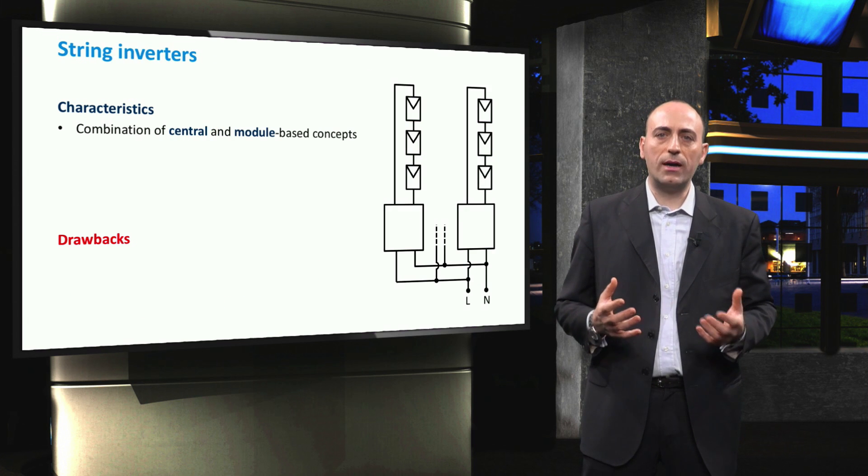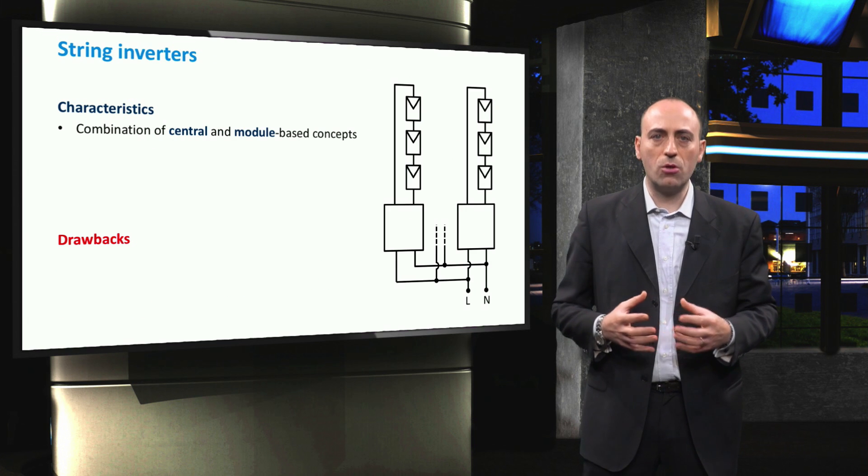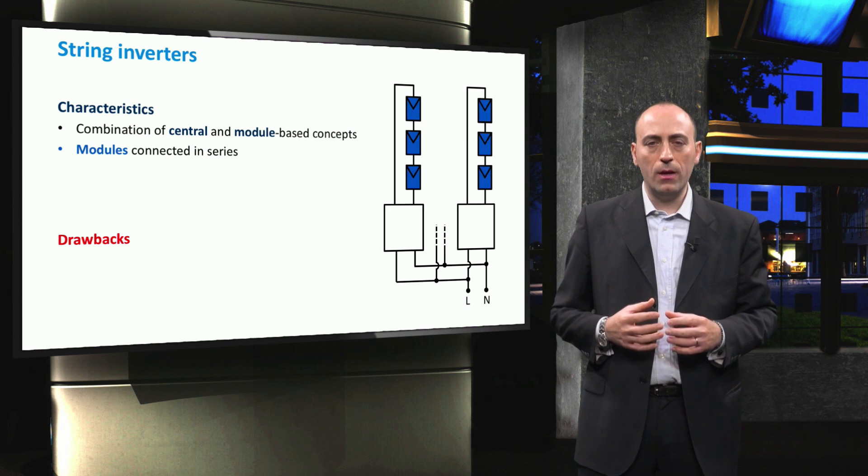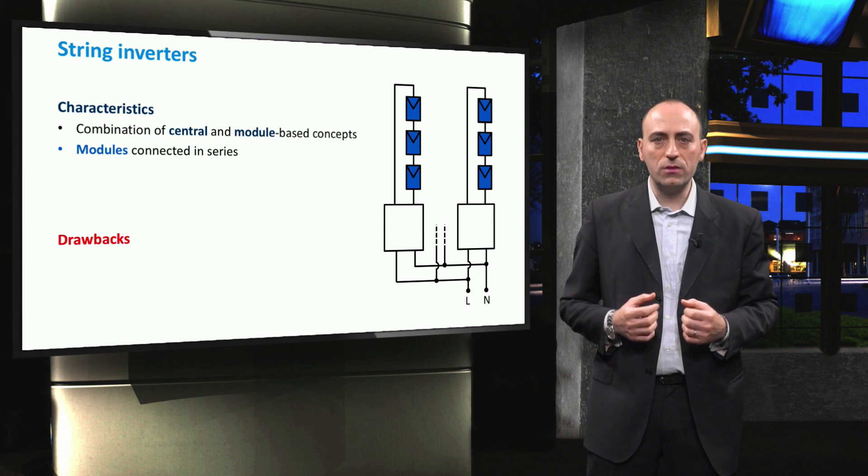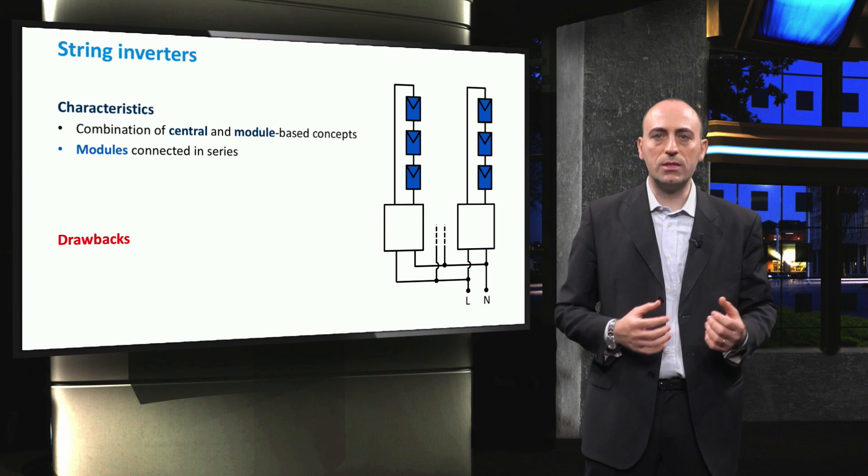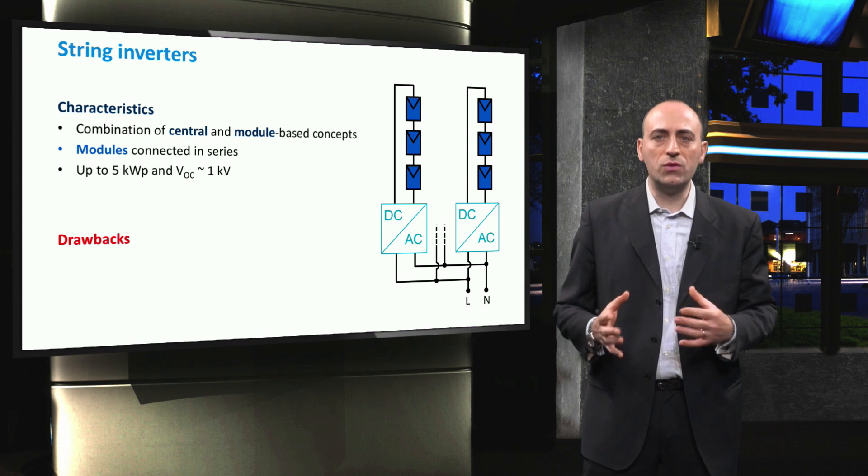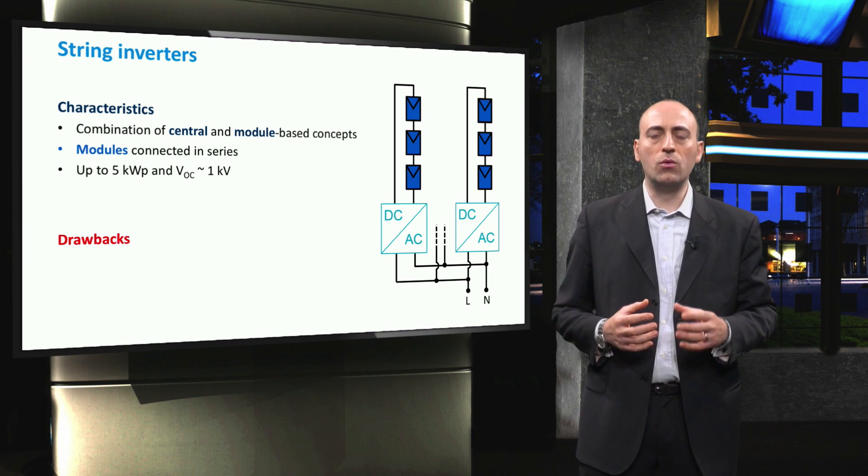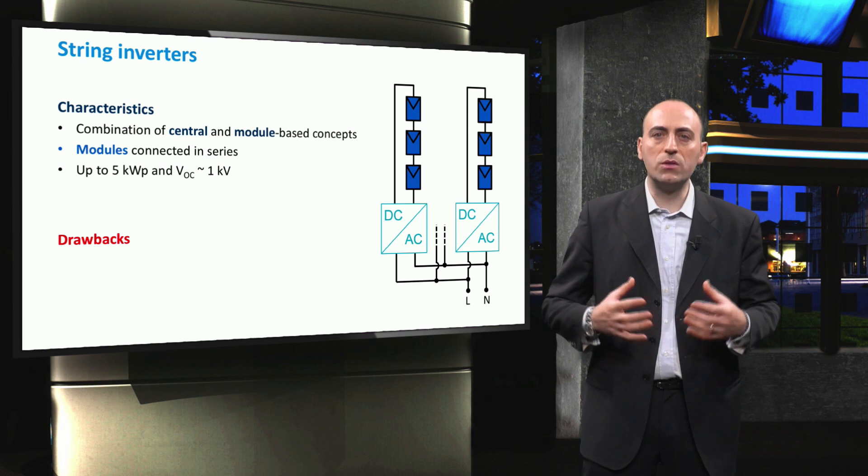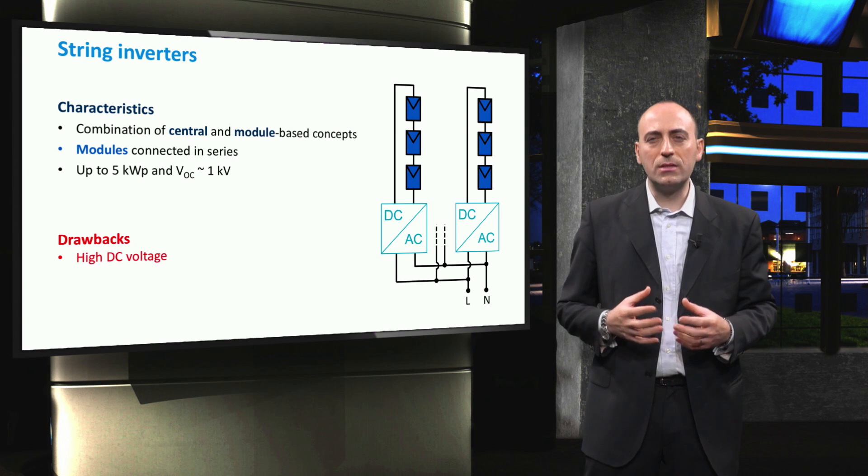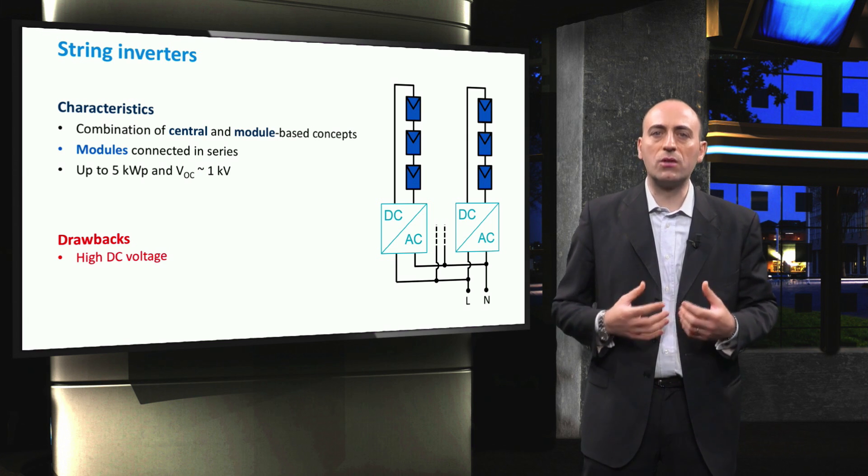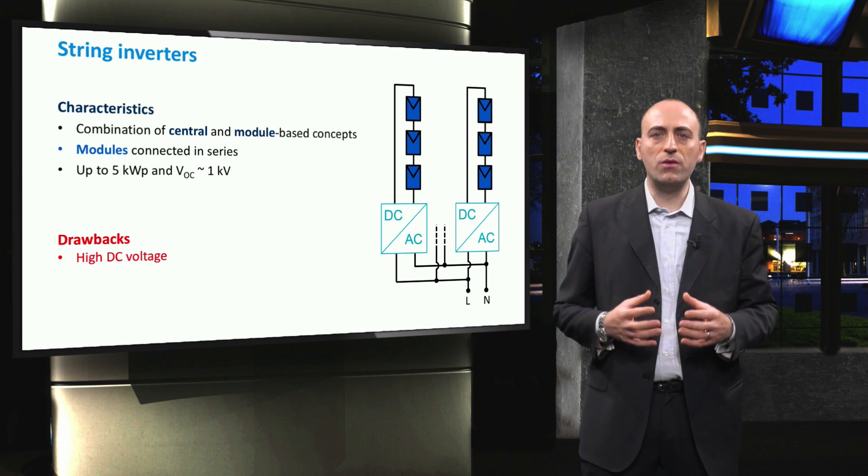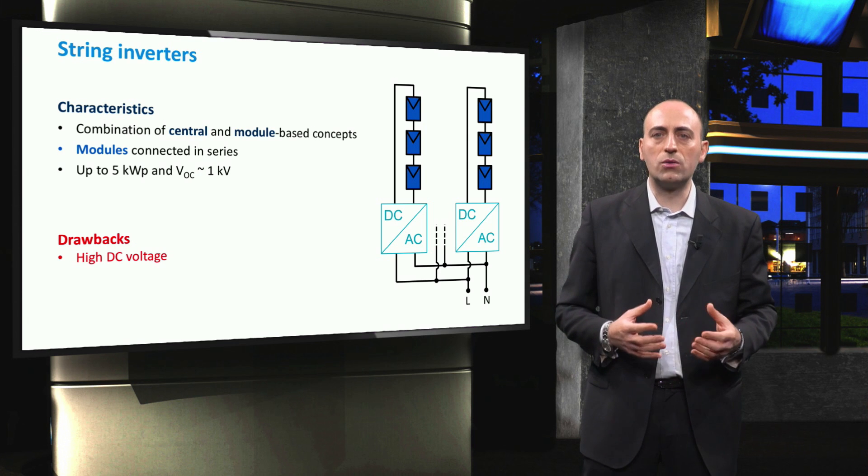The fourth architecture features string inverters, which combine the advantages of central and module integrated concepts with little trade-offs. So here modules are connected in series to form a string, like the central inverter concept, with a power rating of up to 5 to 6 kW peak in one phase configurations, and the open circuit voltage are up to 1 kV, which already exposes one disadvantage of this topology, since high DC voltages require special consideration, as in case of the central inverter architecture. Here this issue is even more important because string inverters are usually being installed in households or in office buildings without designated support structures or increased safety requirements.